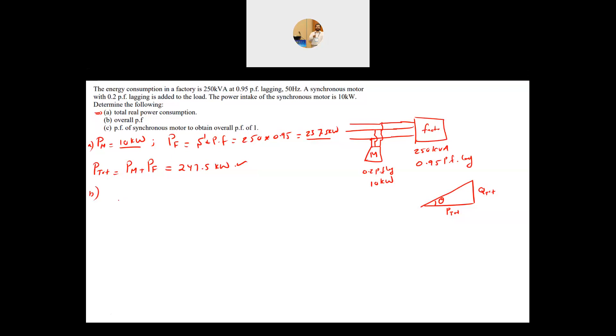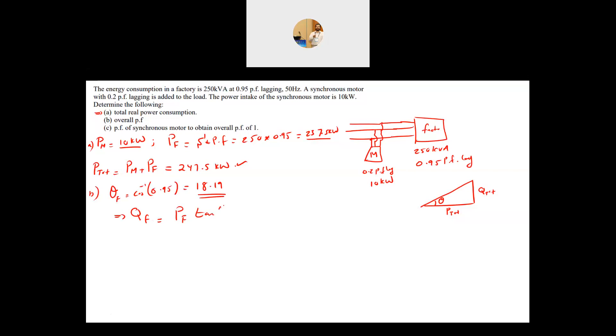Starting with the factory: theta of the factory equals cosine inverse of 0.95, which gives 18.19 degrees. Using the power triangle, Q of the factory equals P_factory times tan(theta_factory), which is 237.5 times tan(18.19 degrees).